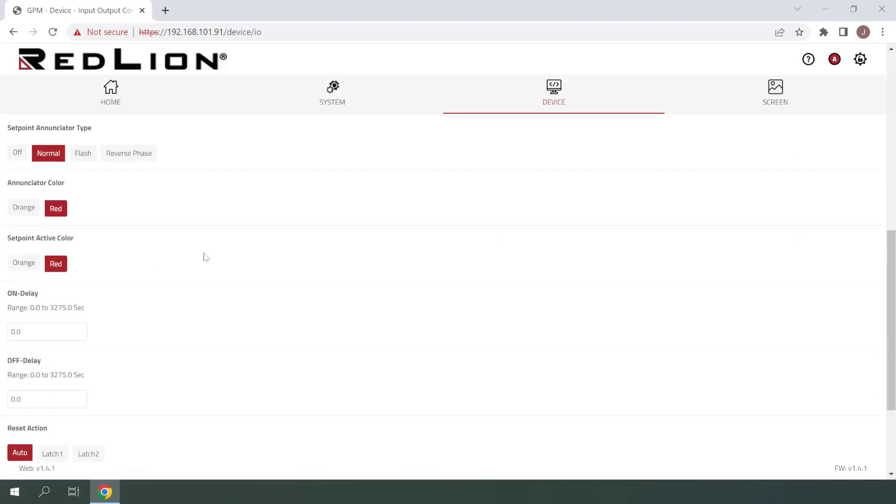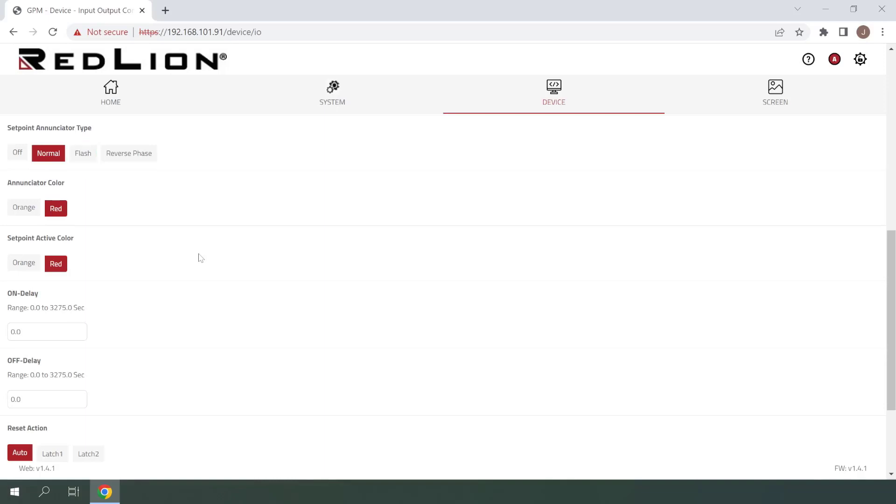The next setting is Setpoint Annunciator Type. If this is set to Off, the annunciator will be removed entirely. If set to Normal, this will be a solid unchanging annunciator when active. If set to Flash, the annunciator will blink on and off when active. Finally, if this is set to Reverse Phase, the annunciator banner will be present only when the setpoint alarm is not active. For this example, I'll be leaving this set to Normal.